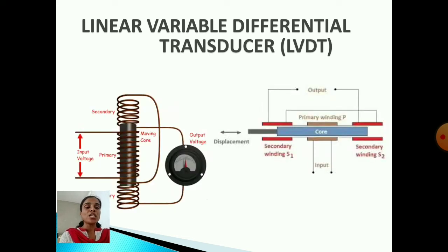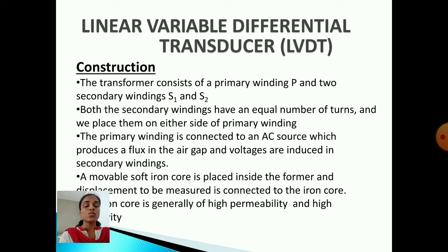Now we are going to see about the construction. It consists of a primary winding and two secondary windings. The secondary windings have an equal number of turns. The primary winding is placed between the secondary windings on either side. A core is used to transfer the electromagnetic field from the primary winding to the secondary windings. We name the primary winding as P and the secondary windings as S1 and S2.